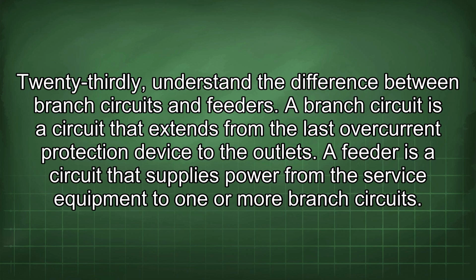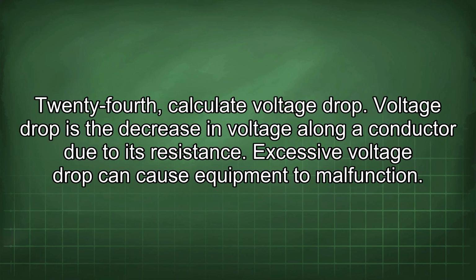23rd, understand the difference between branch circuits and feeders. A branch circuit is a circuit that extends from the last overcurrent protection device to the outlets. A feeder is a circuit that supplies power from the service equipment to one or more branch circuits. 24th, calculate voltage drop. Voltage drop is the decrease in voltage along a conductor due to its resistance. Excessive voltage drop can cause equipment to malfunction.